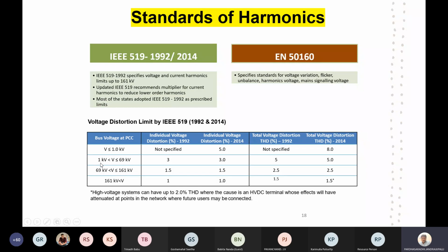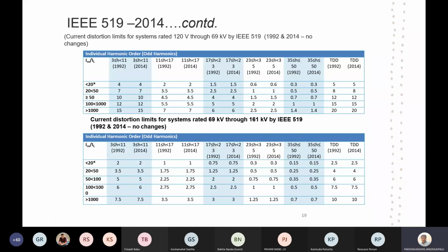Whereas from 1 kV to 69 kV, the individual voltage distortion should be 3%. According to 2014, the total voltage distortion should be 5%. Whereas from 69 to 161 kV, THD should be 2.5%. For more than 161 kV, like 400 kV or 220 kV, it should be between 1 and 1.5%. This is very much required. Now, this is about current harmonics.